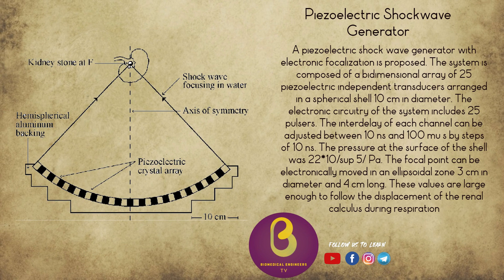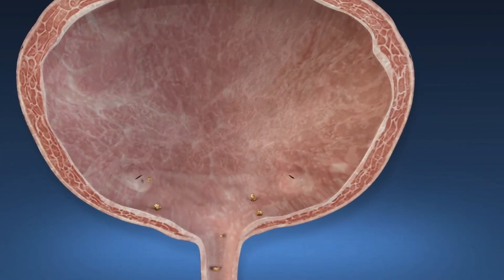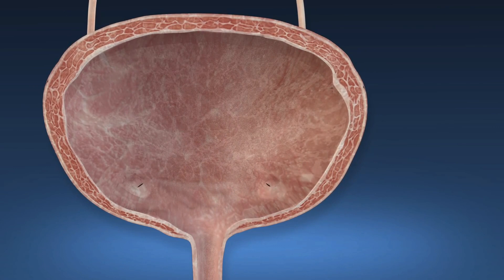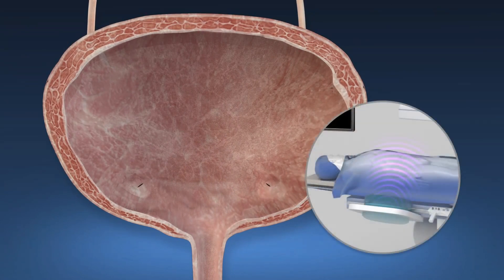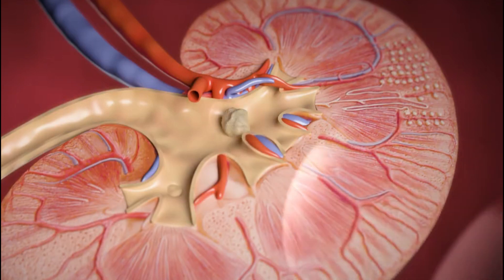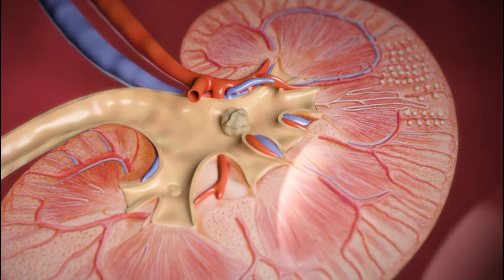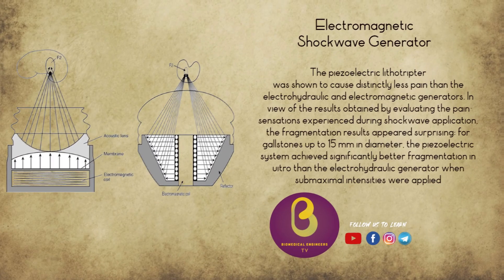The Curie brothers first demonstrated the piezoelectric effect in 1880. The following year, Gabriel Lippmann theorized the reversibility of this effect, which was later confirmed by the Curie brothers. The piezoelectric generator takes advantage of this effect: piezoelectric ceramics or crystals set in a water-filled container are stimulated via high frequency electrical pulses. The alternating stress and strain changes in the material create ultrasonic vibrations, resulting in the production of a shockwave.